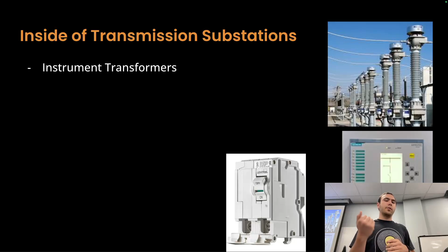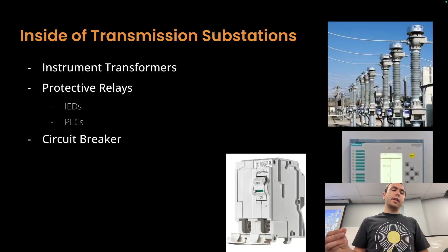Then we have protective relays - these are your IEDs, intelligent electronic devices, and PLCs, the actual controllers, shown as an IED in the bottom right. These are the components that make the decisions inside substations: switching breakers on or off, increasing or decreasing voltage, and so on. You also have circuit breakers, which act like the actuator of the electric grid - they're what actually turns circuits off, which is one of the main functions of the grid.